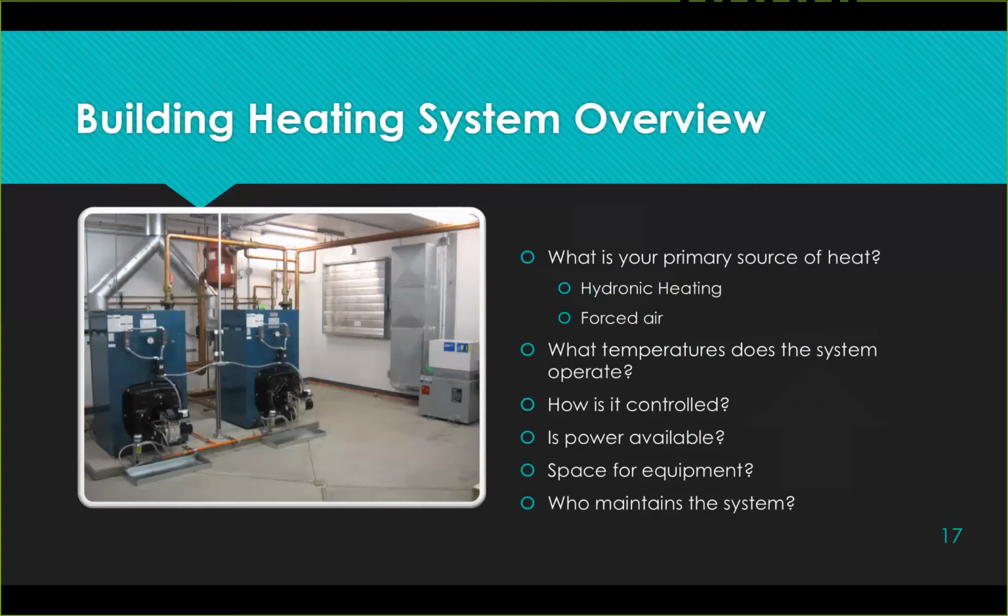So when we look at heating, typically we can pull 190, 195 degree water from our generators and deliver those to a building. If your building's operating at 180, 160, then the higher temps, you can actually include that into your system and take advantage of it. But if you're going to a washateria where they might be putting their building out at 200, 195, 200, maybe you're not getting any advantage from this. It really does play into how your building is. So, look at your building system.